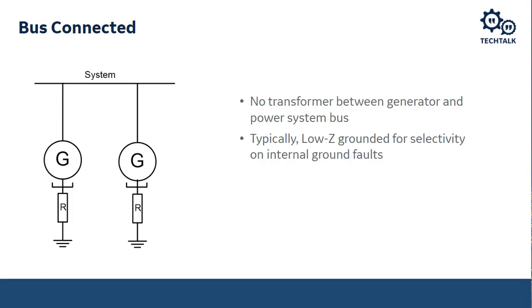So what we have when we talk about multiple generators connected to the same bus are referred to as bus-connected generators. There is no transformer between the generator and the system bus. So these are typically low-Z grounded for selectivity on internal ground faults, because we want to be able to detect not only a ground fault, but where that ground fault is. For a high impedance and ungrounded system, as we'll talk about, we can detect the ground fault, but it's not necessarily going to tell us where that ground fault is. For a low impedance system, not only are we going to be able to detect the ground fault reliably, but we're going to be able to locate the fault, know where that ground fault is.